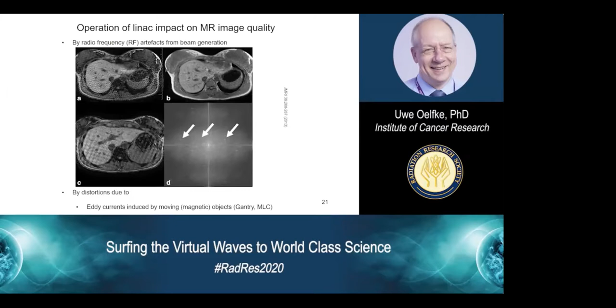And second, let's look at one example of the impact of the operation of the LINAC on the MRI image quality. I think it's pretty clear on these images that you have these speckle and streak artifacts, which you can actually even see in K-space, and they are induced by eddy currents which are caused by moving magnetic objects like the gantry or the MLC in the magnetic field of the MRI.